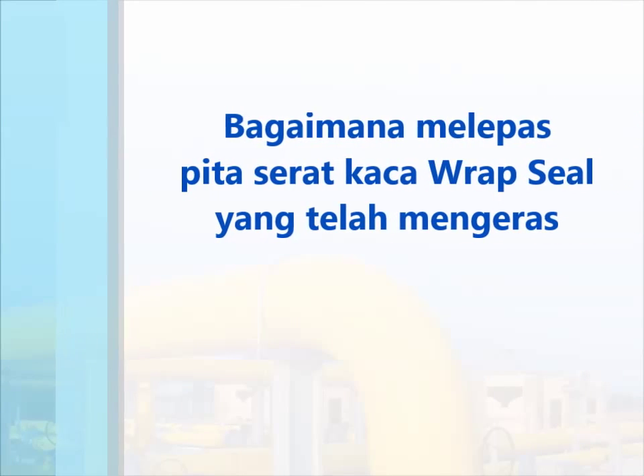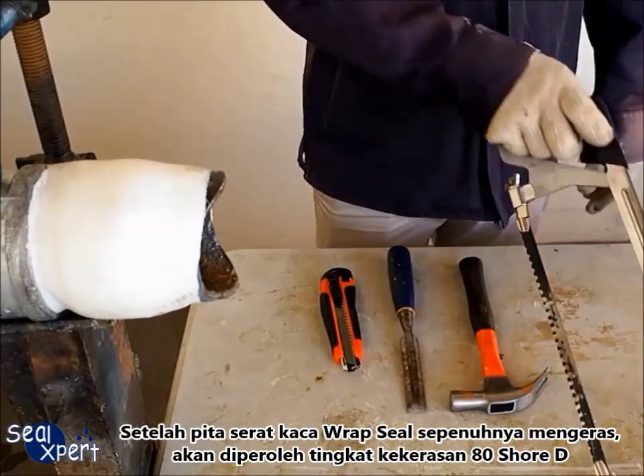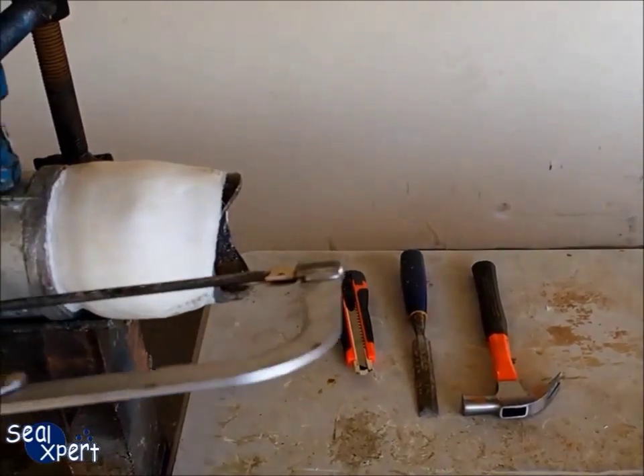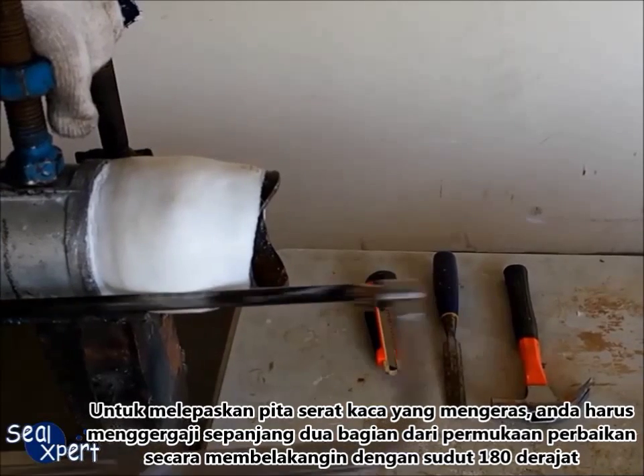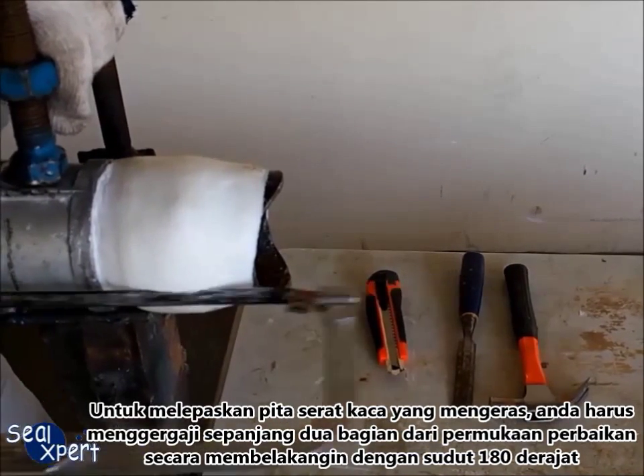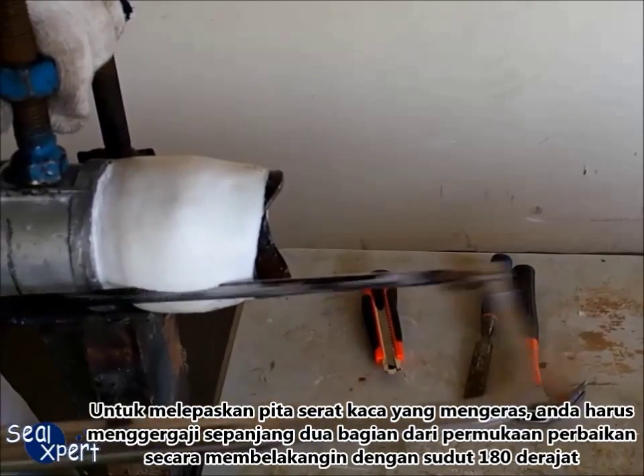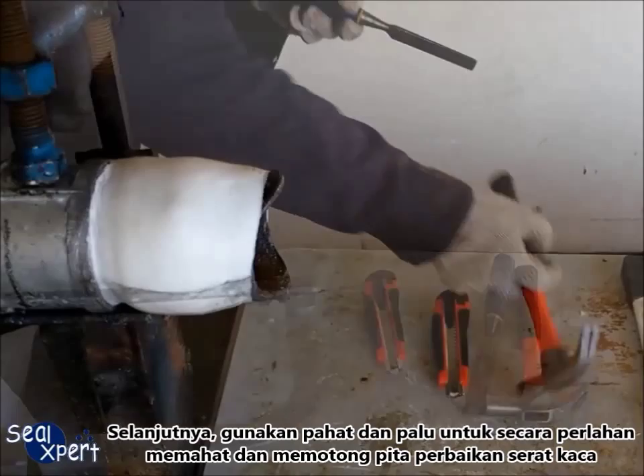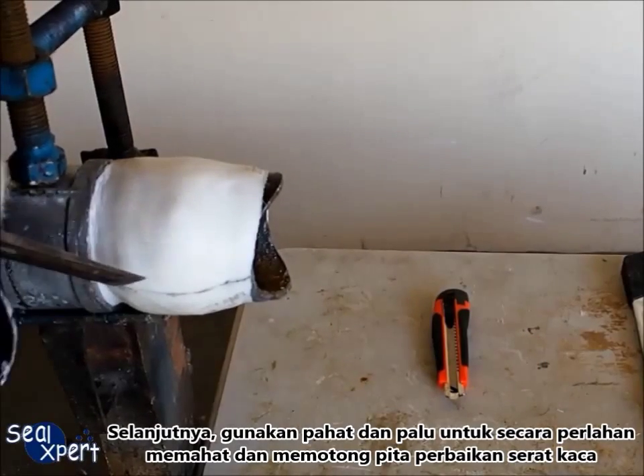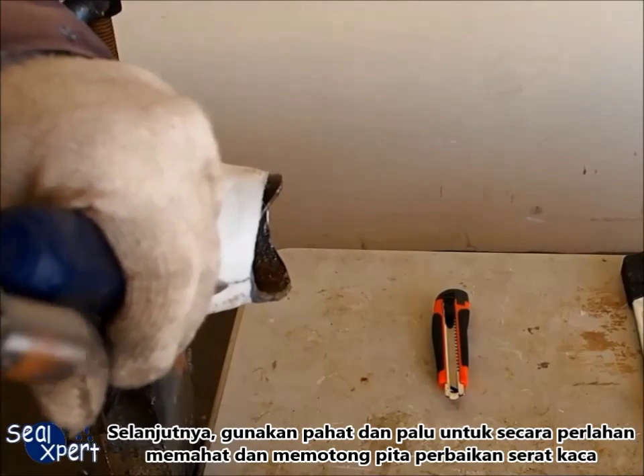After the Wrap Seal fiberglass tape is fully cured, it will attain approximately 80% Shore hardness. In order to remove the cured fiberglass tape, you will need to saw along the two sections of the repaired surface, 180 degrees away from each other. Next, use a chisel and hammer to gently chisel and cut off the fiberglass repair tape.